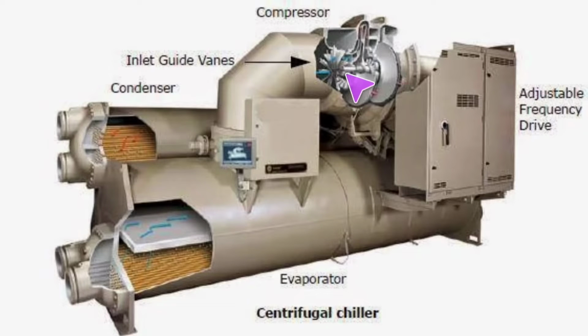Your inlet guide vanes, that's how you control flow through this machine. So basically, this is your load control. This is your unloader solenoid valve. This is your staging of multiple compressors. For example, say it's a two compressor machine. Well, you're going to want to run one compressor for half capacity. Well, instead of killing a compressor, we're controlling these guide vanes.